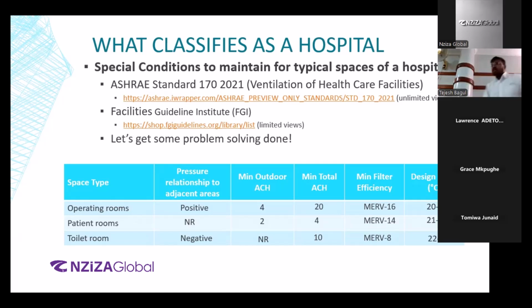Okay, so the next thing is patient rooms. The patient rooms will usually have an isolation area, right? There will be a patient room. If guests are visiting the patient, they will need to go through an isolation area, also called an anteroom, so that the amount of cross-contamination between the corridor and the patient recovery room is reduced as much as possible. In that case, we have the NR. NR is not required. Okay.